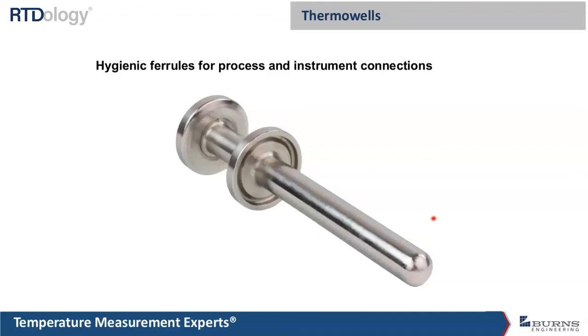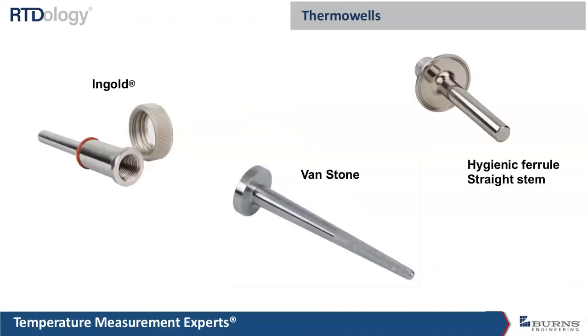If we go back to a well like this, where it looks like a mirror finish and you can see yourself in it, this one's probably down around a 10 micro-inch finish. So that's just a quick way to estimate surface finish if you're trying to replace an existing well with a new one.